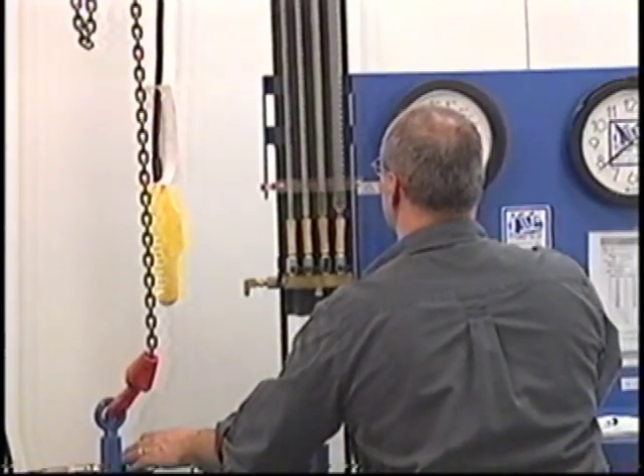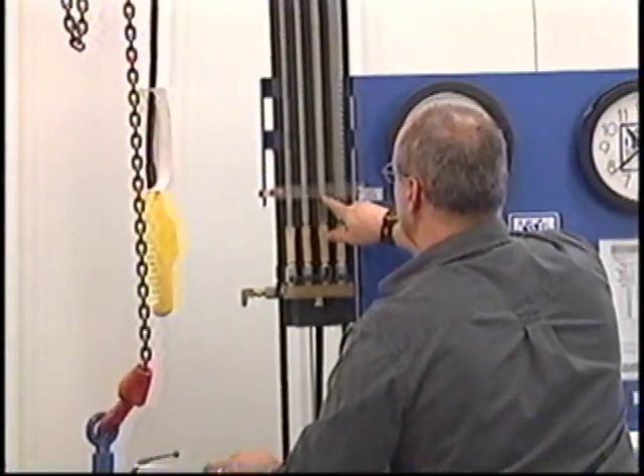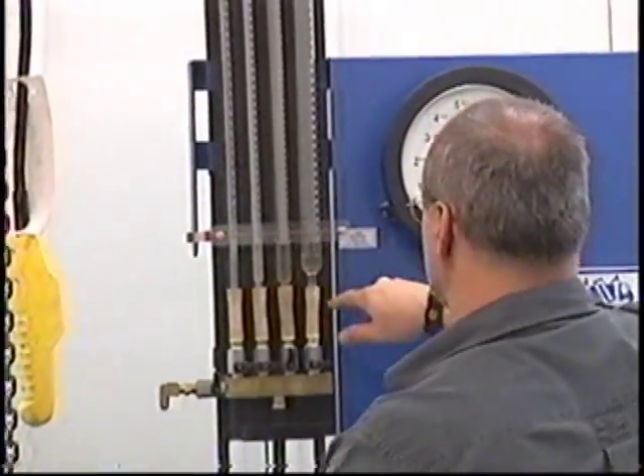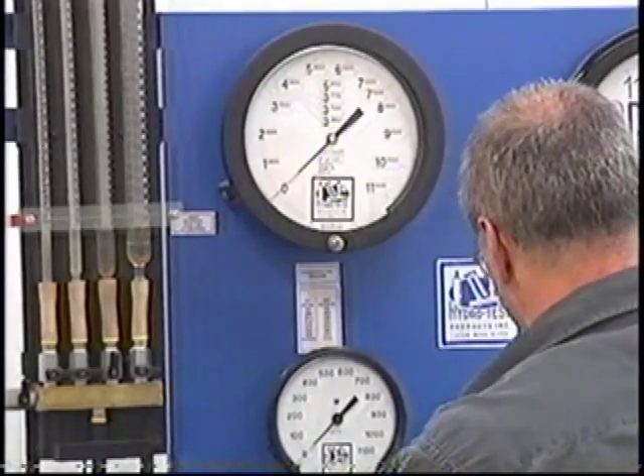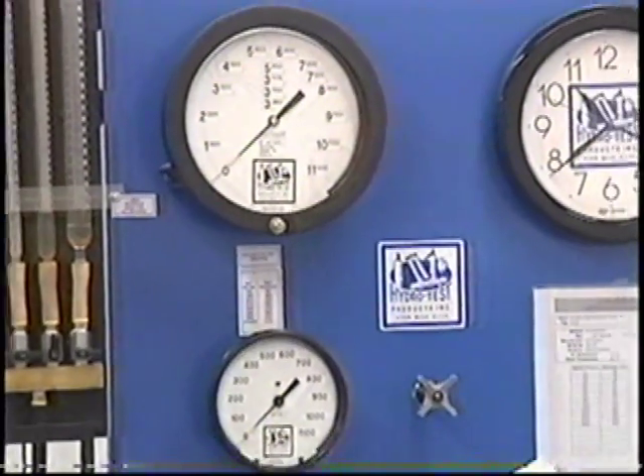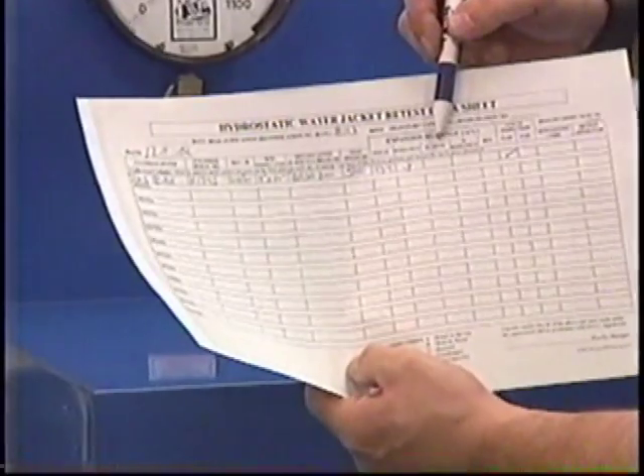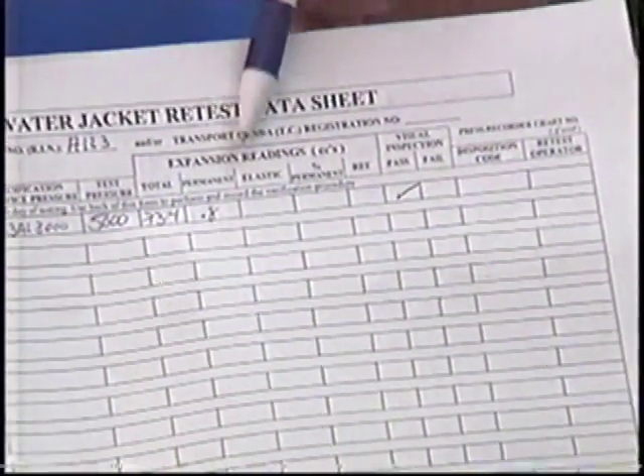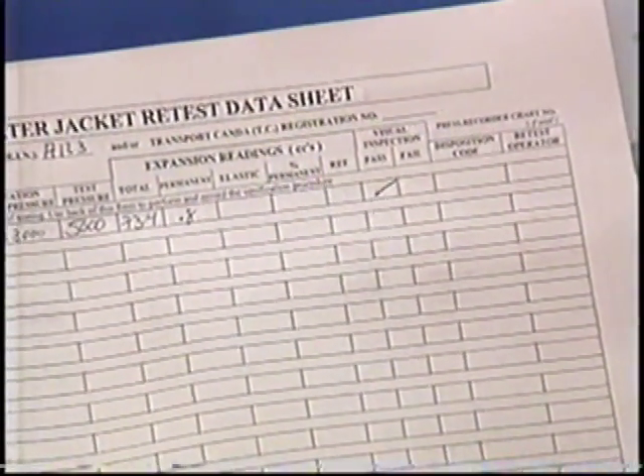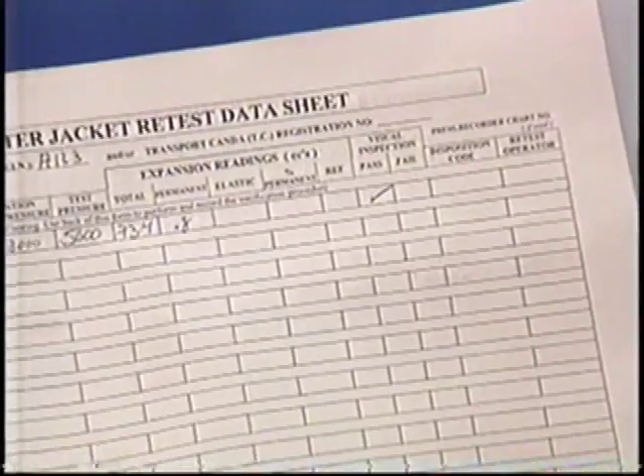And in this case we have 0.8 cc's of permanent expansion. We write that figure in. A little bit more math, we now need to figure out what the elastic expansion is, and that is the difference between the total and the permanent. To get that figure we take 73.4 minus 0.8, and that gives us 72.6.